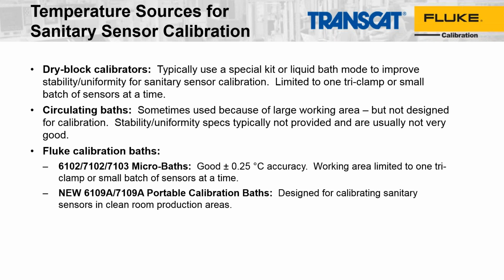Sometimes there are some hybrids where they are dry block calibrators, but they will have a small well filled with fluid so that a temperature sensor can be put into it. But usually the inserts or the blocks are fairly small dimensionally, so they can only accommodate one sensor at a time, just because of the size of the transmitter head, or the size of the flange on the tri-clamp sensor. Circulating baths are also sometimes used.